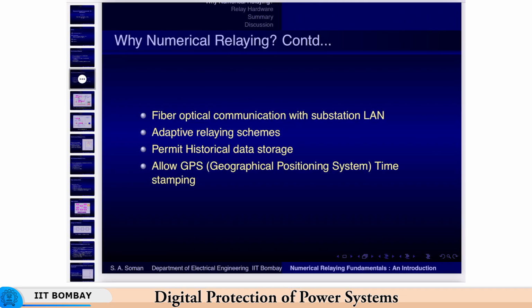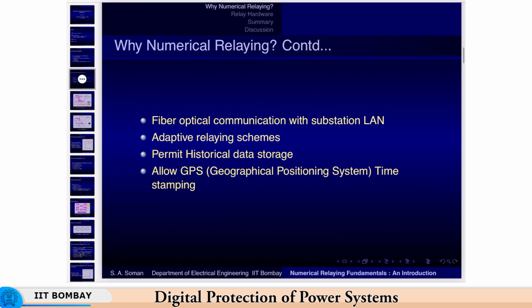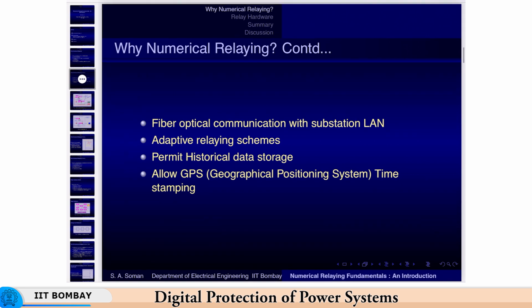For example, in the night your load is very low, so your generation is low, and your settings may need to change. With numerical relays that is possible. There are things known as group settings, where you have one group of settings for one particular condition, another group for another condition, and with an external trigger like a digital input, such as a breaker status change, you can wire it to change the settings according to the change in the network conditions. So that is adaptive relaying - it adapts to changes in settings.